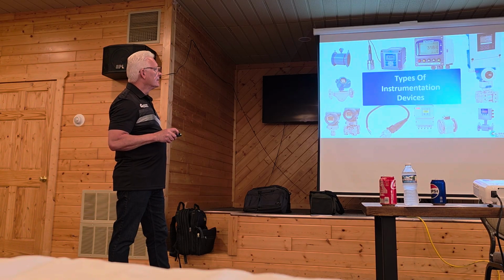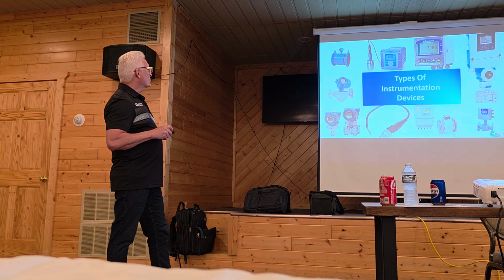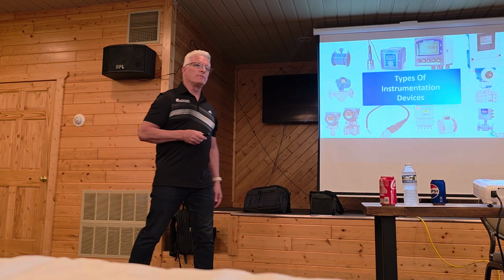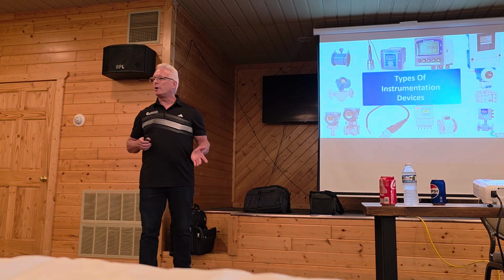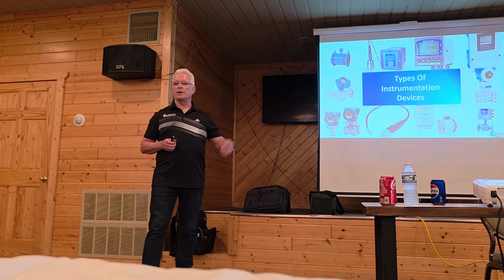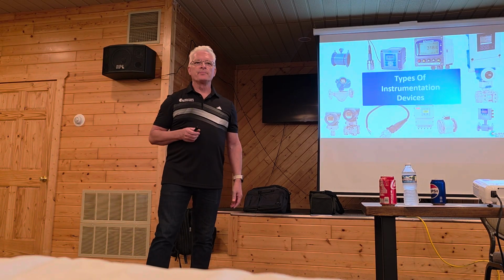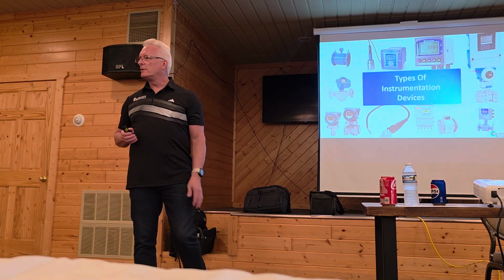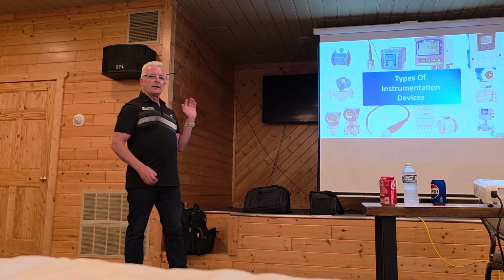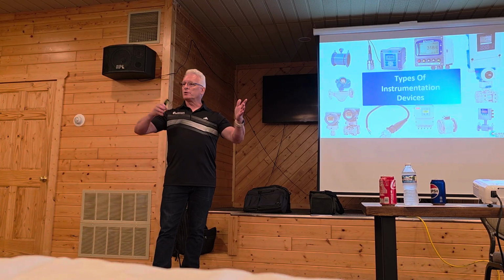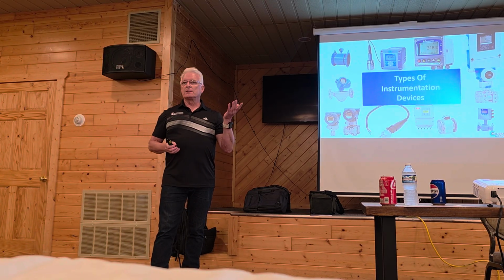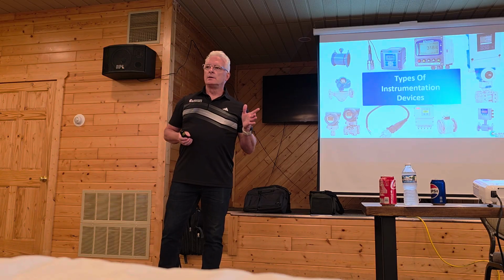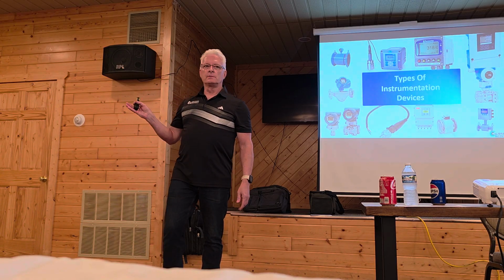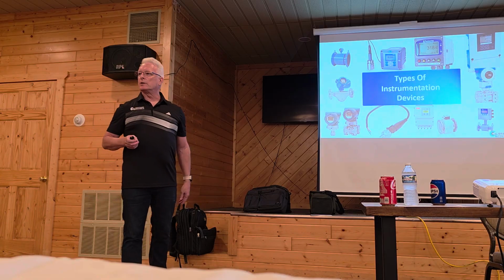Endress+Hauser mag meter, another Endress+Hauser, Badger, ABB, these are Yokogawa, and a Rosemount Coriolis meter. Coriolis meters are very, very, very, very accurate. You won't see that in the water industry. Usually in pharmaceuticals, they're like 0.01 accuracy. A mag meter is about a half, so 0.5. So big difference. So if you had a mag meter 4-inch and a Coriolis, the mag meter list would probably be around 5,000 to 6,000. A Coriolis 10,000 to 15,000. So a big difference, and it's not necessary in the water industry.